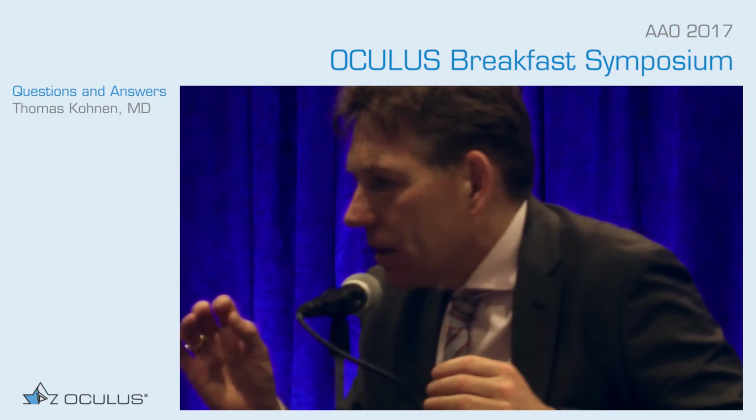There was a slight difference with opacification. I mean, with the 500, you sometimes don't get the IOL Master 500 measurement. You cannot screen every cataract, but I think with the AXL and the 700, it's very close. So it's an improvement again. And the advantage here is now you have in your device, as you also pointed out, the axial length, and Oculus have done that perfectly.